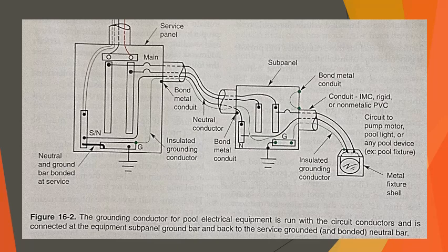Also, the grounding conductor must be insulated and run in conduit with the circuit conductors all the way back to the supply panel ground or the supply panel grounding terminal block. Figure 16-2 shows the correct way to ground electrical equipment in and around the swimming pool.